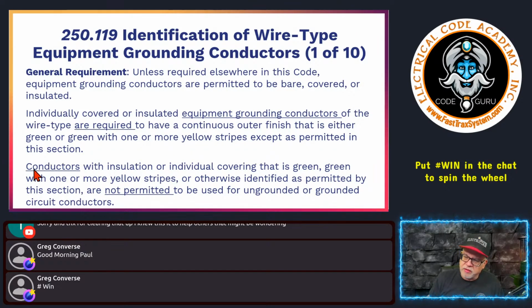Next it says conductors with insulation or individual covering that is green with one or more yellow stripes, or otherwise identified as permitted by this section, are not permitted to be used for ungrounded, that's hot, or grounded neutral conductors. Grounded is to say not all grounded conductors are neutral, but all neutral conductors are grounded, okay?